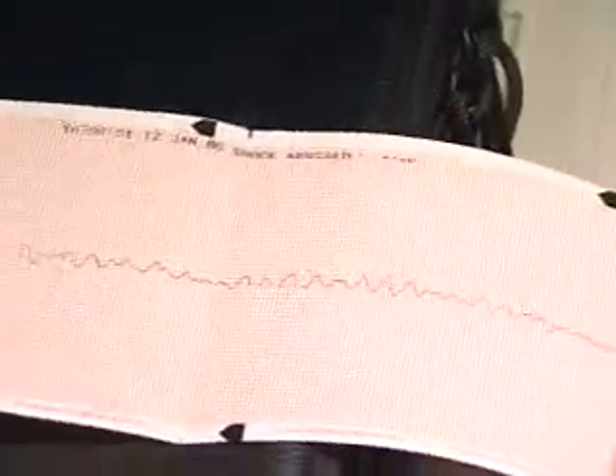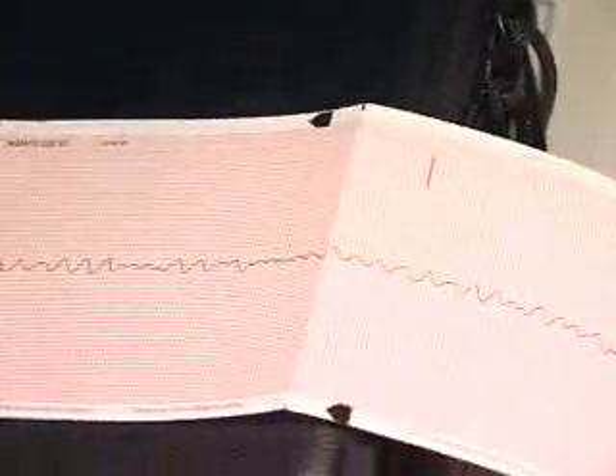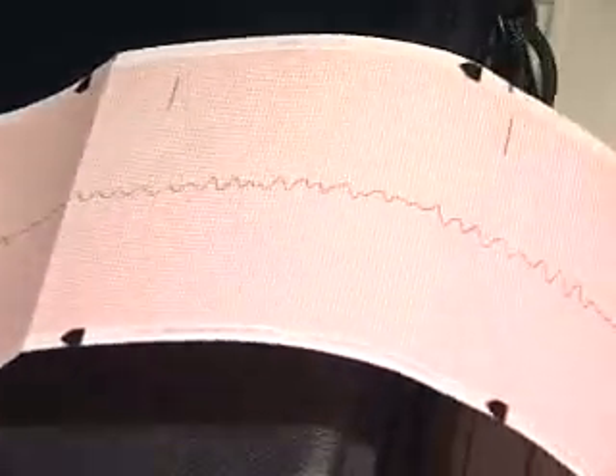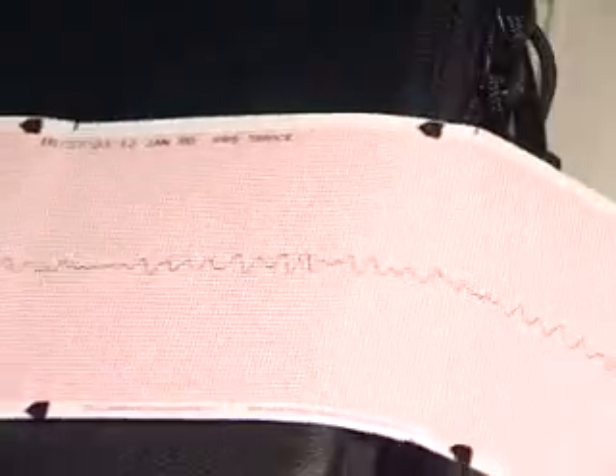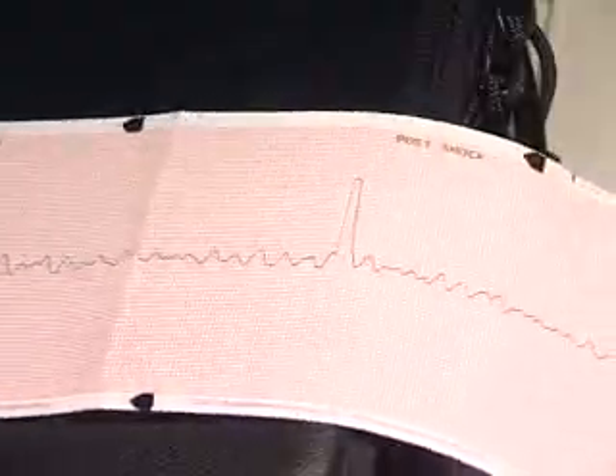The Summary Report function allows you to store and retrieve ECG and device event information. The internal device memory automatically records defibrillation and cardioversion segments, heart rate alarm, and ECG segments. With Pace option, it will also store Pacer mode. Associated event information such as device settings, patient ECG, time and date, and code markers are also recorded. The Summary Report records each event in chronological order and stores up to 250 defibrillator or 210 recorder-activated ECG events.